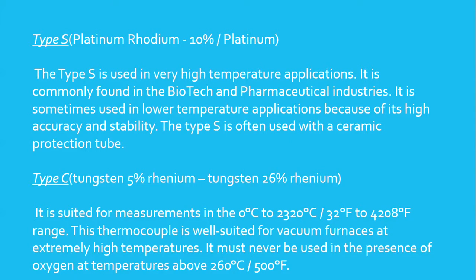Type S. The Type S is used in very high temperature applications. It is commonly found in the biotech and pharmaceutical industry. It is sometimes used in lower temperature applications because of its high accuracy and stability. The Type S is often used with a ceramic protection tube.